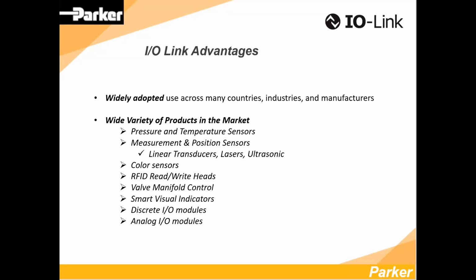A lot of sensors that were traditionally analog will come in an IOLink version. But if by chance it doesn't, there are IOLink to analog modules. So you still don't have to buy the PLC analog card, you still don't have to route shielded cables or worry about induced noise issues. You can buy an analog IOLink module, put it out close to the source to reduce that analog cable length down to almost nothing, and then it's IOLink - virtually noise immune.